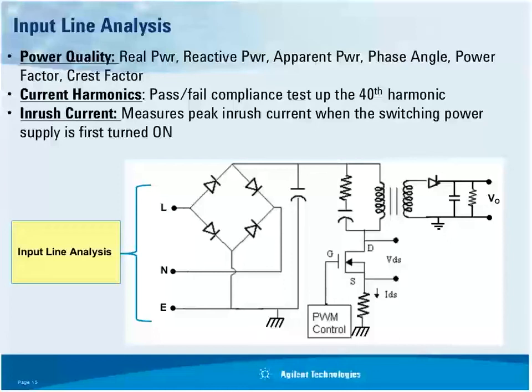Let's take a look at input line analysis — making measurements on your AC input. One measurement is power quality: the scope automatically measures real power, reactive power, apparent power, phase angle, power factor, and crest factor. Current harmonics is the only test among all these that I would term a compliance test — it must meet a particular standard. And then there's inrush current.